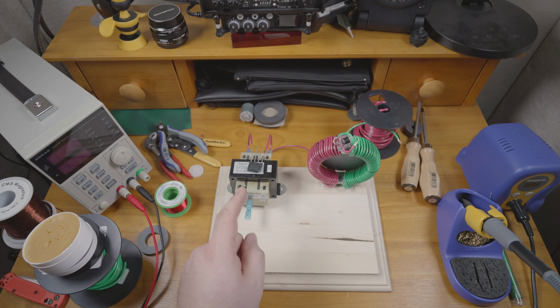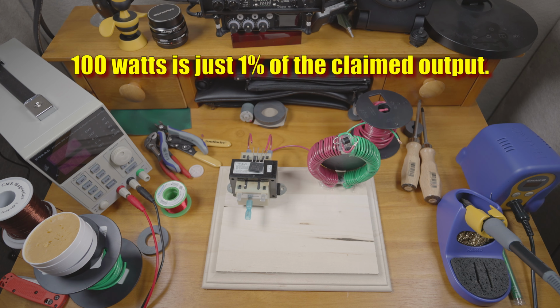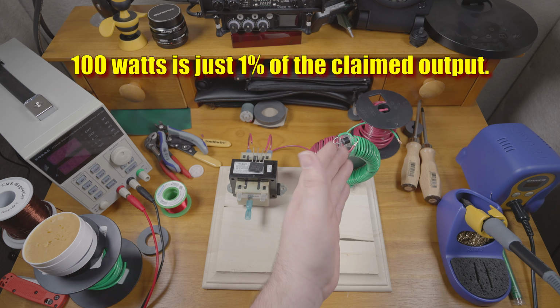Our little bearing coils are connected to the 12-volt side of the transformer. That insinuates the expected voltage created by the coils would be around 12 volts before going to the transformer and being stepped up from 12 to 220 volts. So the implication is these coils are producing 10,000 watts at 12 volts. But 10,000 watts at 12 volts is over 800 amps. Even 100 watts at 12 volts is over 8 amps, which is 30% more than the diode can handle, twice what the rectifier can handle, and twice what this transformer can handle. It's just staggeringly absurd. But let's keep going.